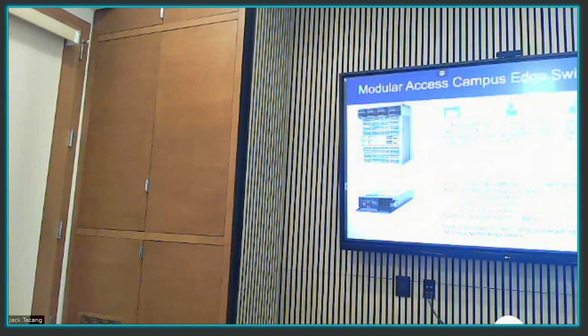And that's where these modular access type switches come in, right? Because the power supplies in these things are rated for 3200 watts each, and there are 8 of them in that unit. This manufacturer isn't the only one that makes them, there are multiple manufacturers that make these boxes. That's why they're making these modular access switches, basically to handle loads you can't get from the 1U switches.